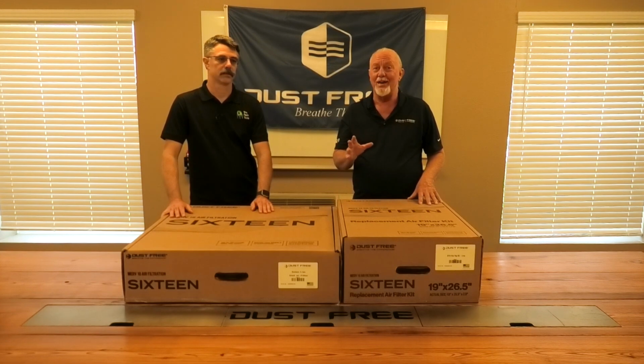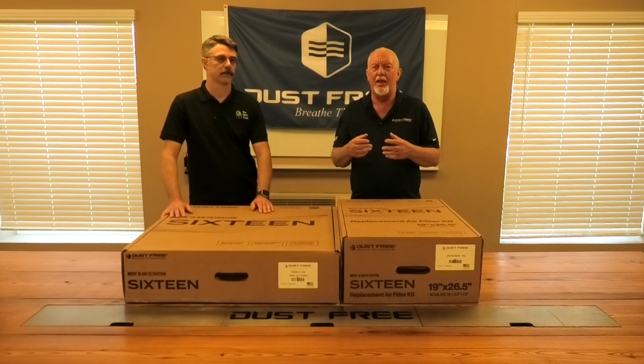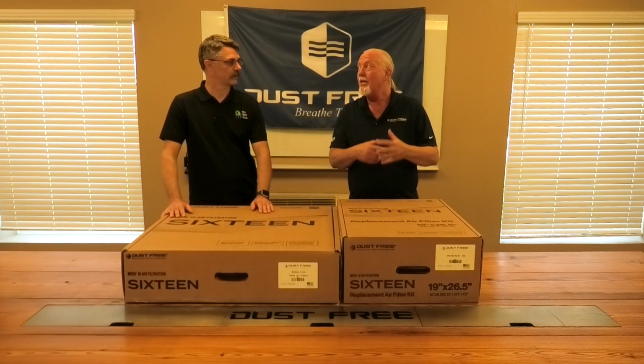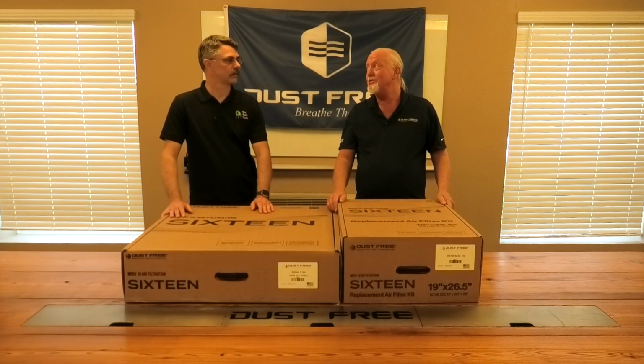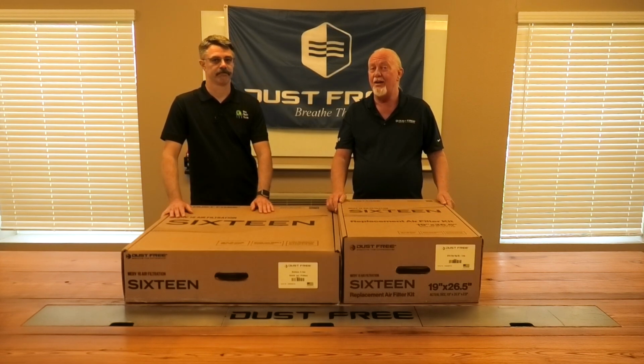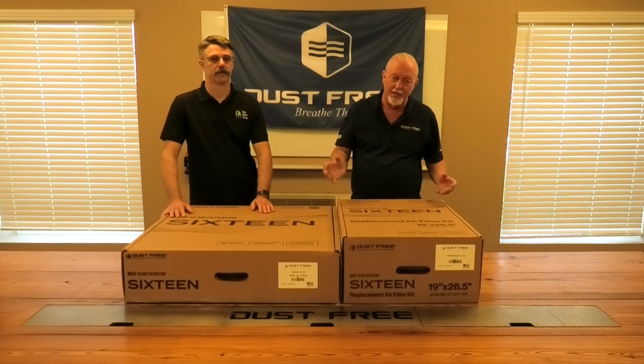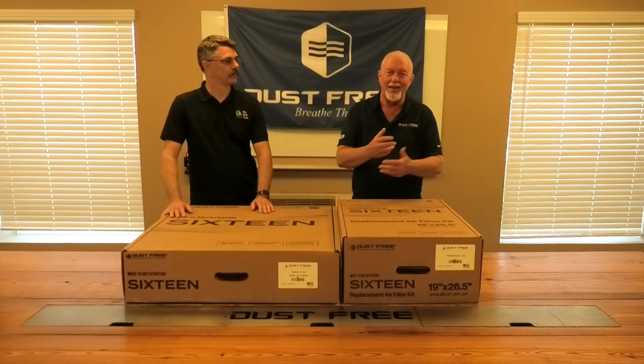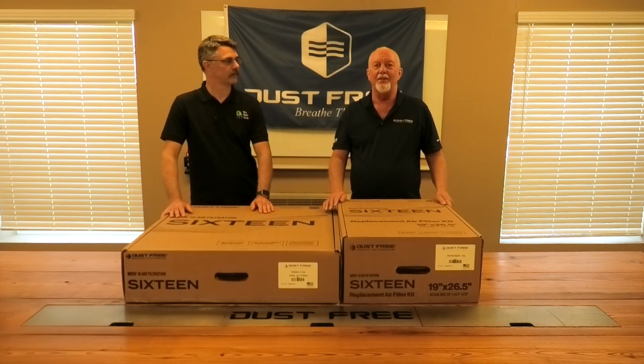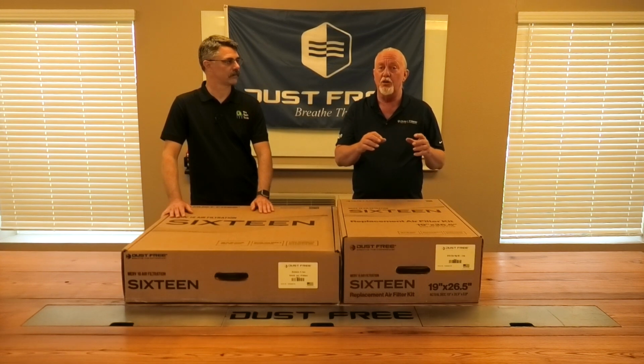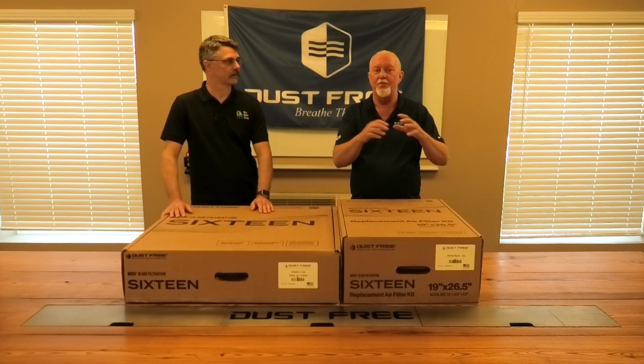Historically, what we've got on the market now is a panel filter, and it's extended pleated, so it's like 4 or 5 inch, and we are achieving a MERV 16 rating, but the static resistance is pretty up there. As we're looking at system performance and delivered airflow, and of course sensible, latent and static pressure, that is huge, because when you take a big bite out of your static pressure budget, that really starts putting restraints on how you design the rest of your equipment.